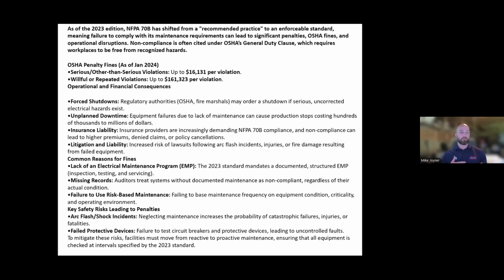But the main reason we're doing these shutdowns is for your equipment. Your equipment needs to be maintained. You don't want any kind of unplanned downtime, or any kind of fault down the line that could increase the risk of an arc flash or a fault, shutting down your actual switchgear when it's not planned. You'd rather be proactive than reactive. OSHA is now implementing this so it can force your hand in order to do so.